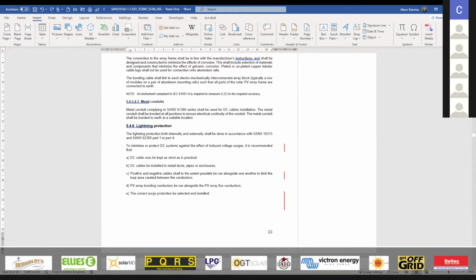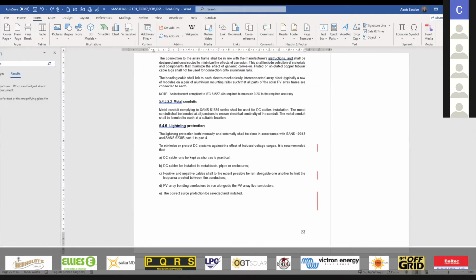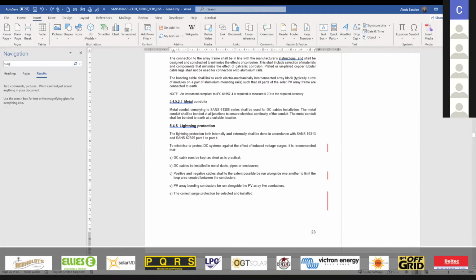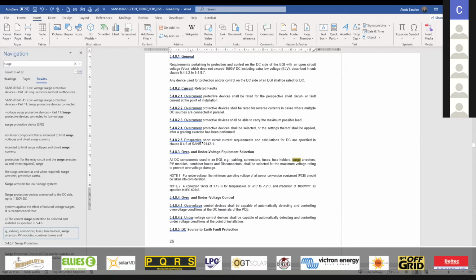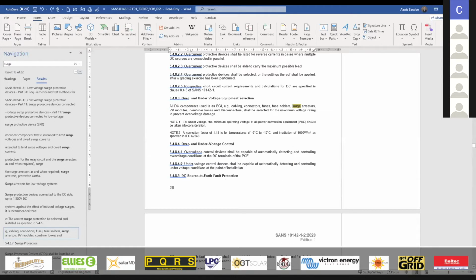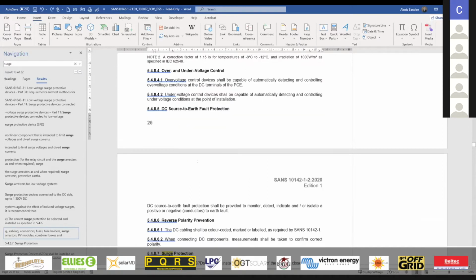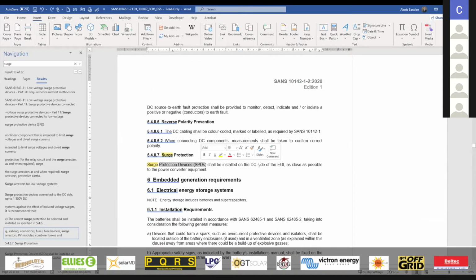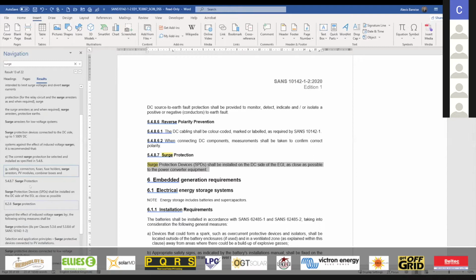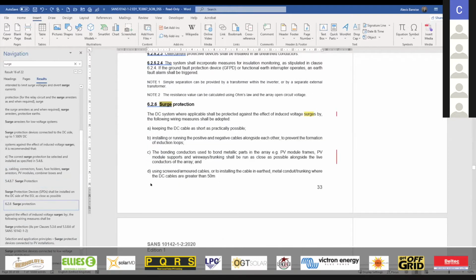And the last part is to fit the correct surge protection devices, so they have to be correctly selected and also installed. And there's a drawing given in this standard, and I'll show that to you just now. An interesting part about surge protection as well is that we have made it a mandatory item that a surge protection device be installed on the DC side of embedded generators. So that's not even a choice. You have to do that, but you also have to understand which one to use. And I'm going to show you in the drawing.